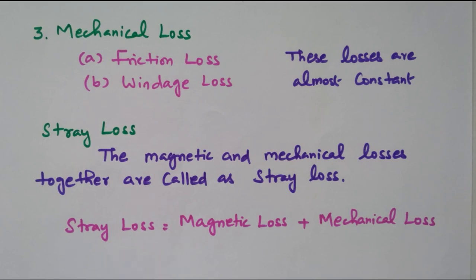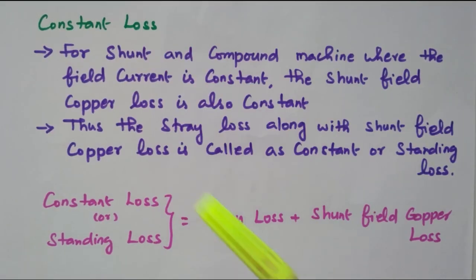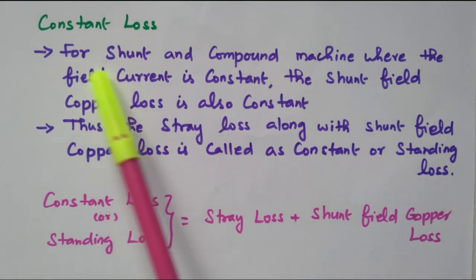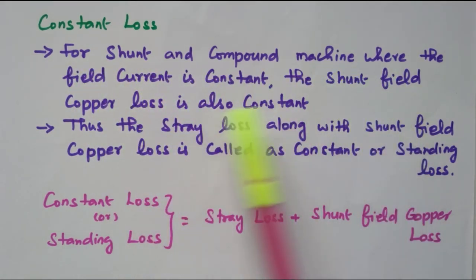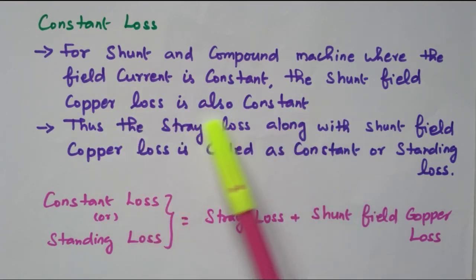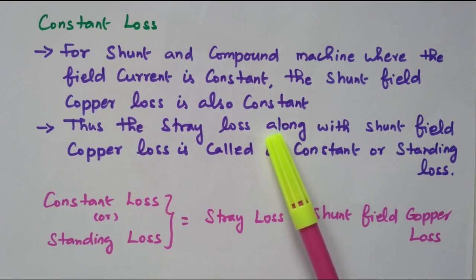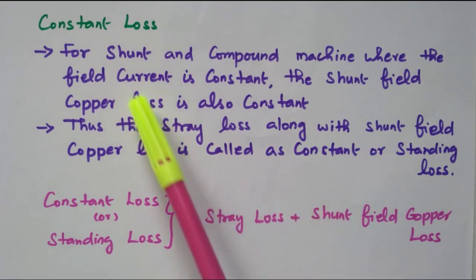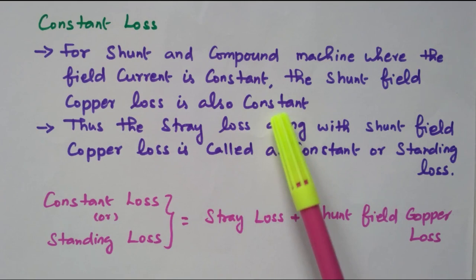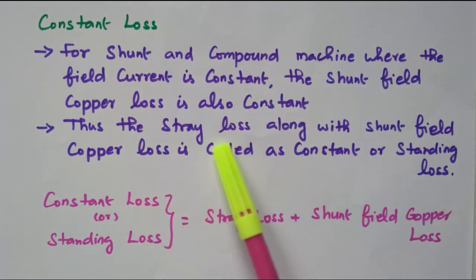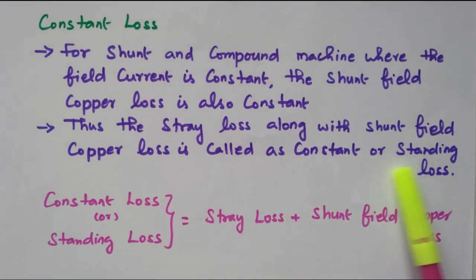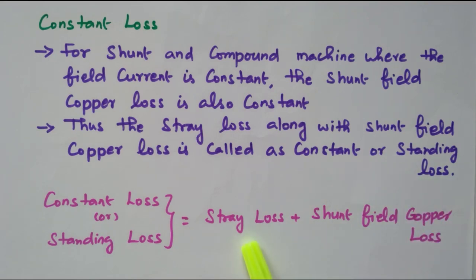Now we will go for further classification. We have one more constant loss. In shunt and compound machines where the field current is constant, the shunt field copper loss is almost constant. Only a very small amount of current flows through the shunt field winding, and it does not vary. So the stray loss along with the shunt field copper loss is called constant loss or standing loss. It will not vary with the load.